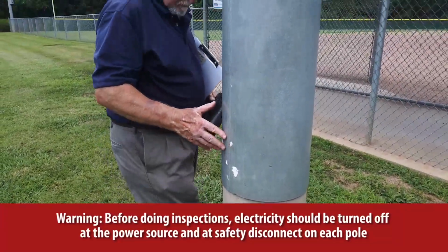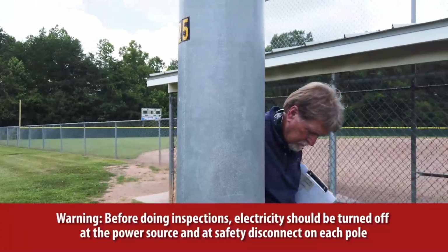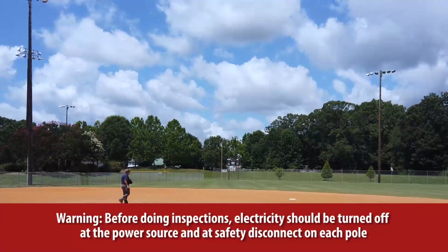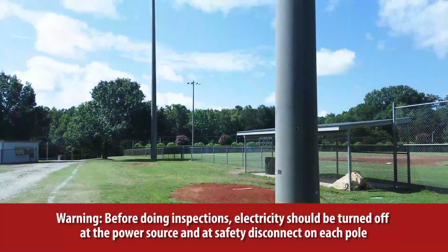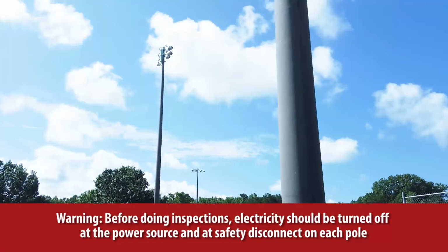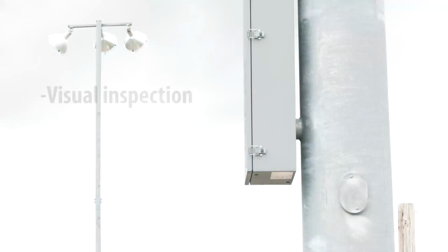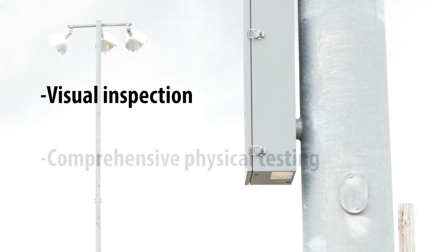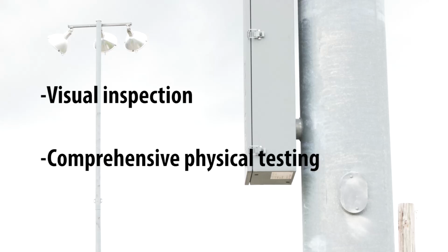Inspecting your lighting system's poles is vital in order to ensure correct structural integrity, safety at your facility, and monitor how they're holding up to environmental elements like wind and water. Most poles are constructed of either wood, concrete, or steel. There are two key steps in checking your poles: a visual inspection and then a more comprehensive physical testing depending on what type of poles you're working with.